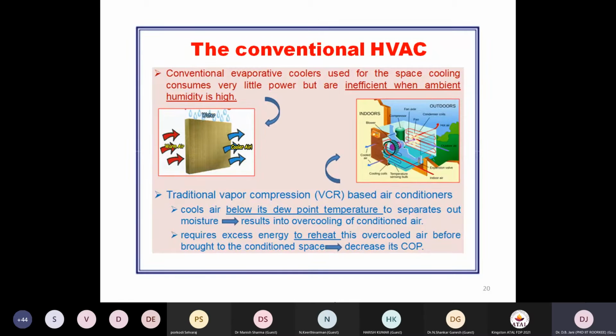So both systems, whether evaporative, have their climatic applicability, while evaporative systems are inefficient when ambient humidity is very high. Typically in the area where you are residing, Chennai, almost all days of the year have humidity in the range above 80 to 85 percent. In summer, in June or August, humidity may be above 90 percent. That is too much, concerning the health of humans. In the coming slides, we will see that.